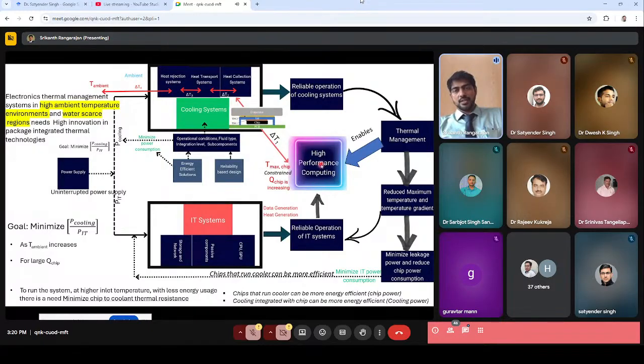So if you want to achieve a thermal resistance of 0.03 for this entire data center put together, what's in close proximity to the high performance computing chip is the heat collection system—often cold plates or heat sinks. Then you have the heat transport systems, which are the coolant distribution unit circulating the coolant. Then you have the heat rejection systems, which are the cooling tower or dry coolers, and then the ambient. So from the high performance computing chip, the heat has to travel through all of the system before it reaches the ambient.